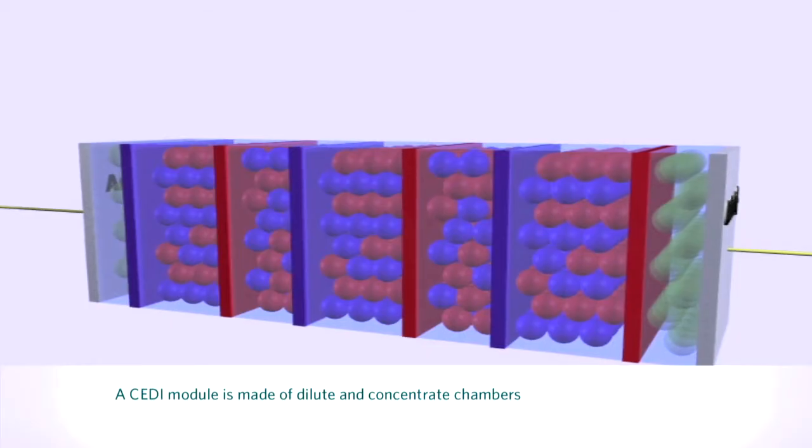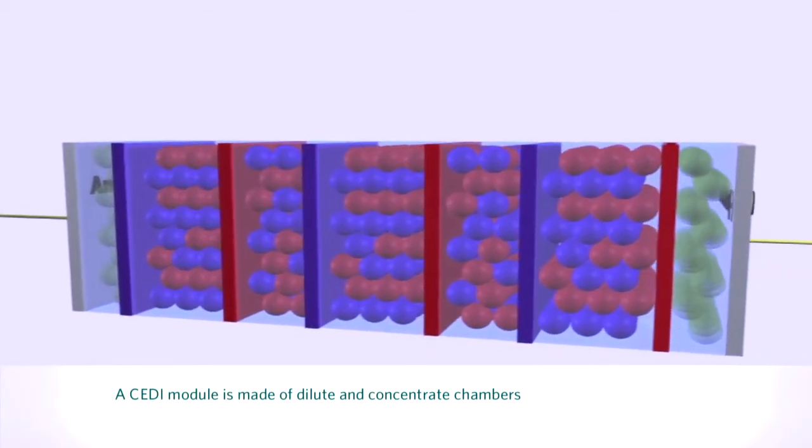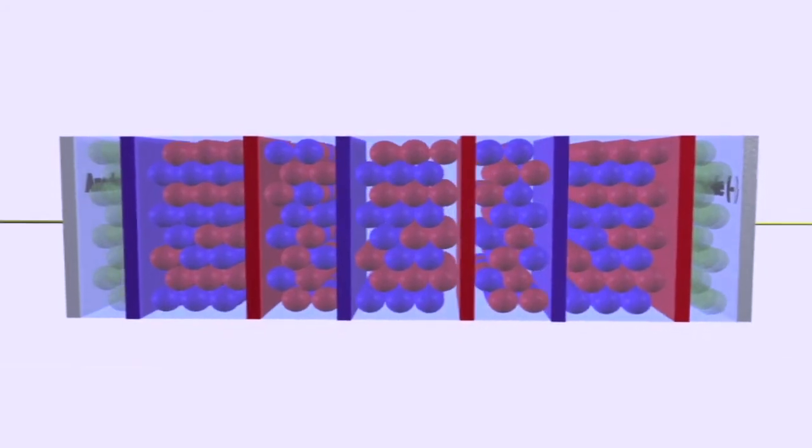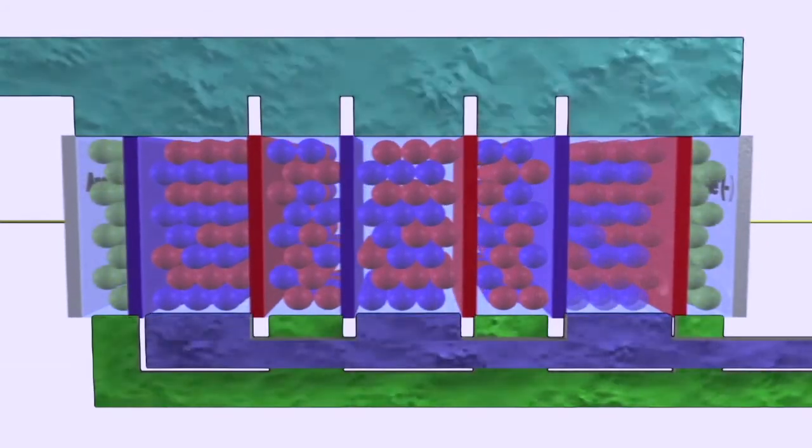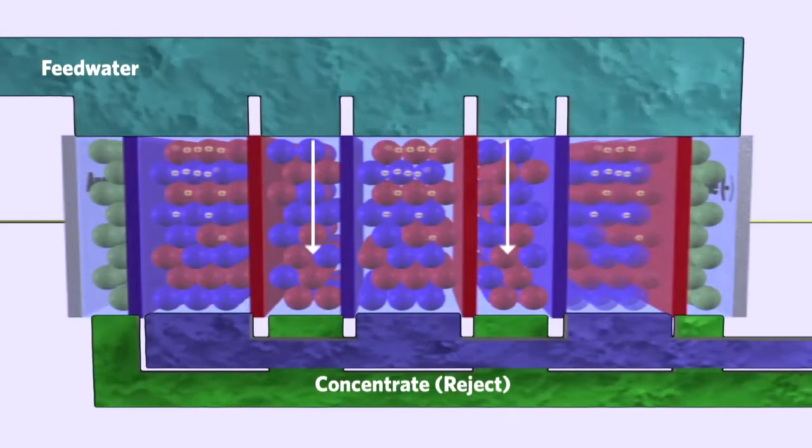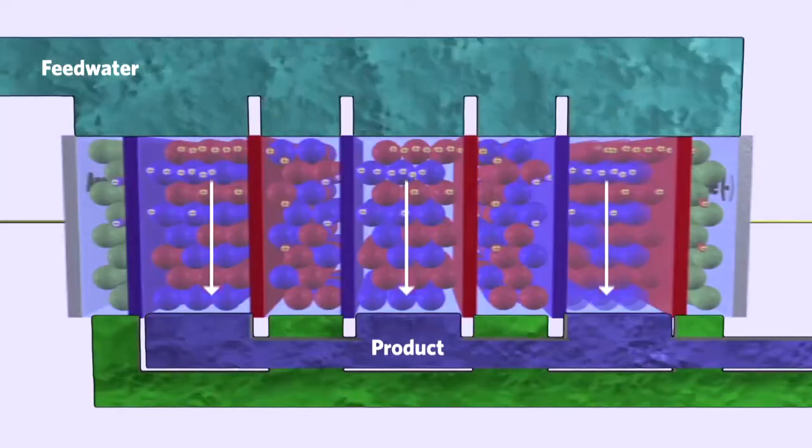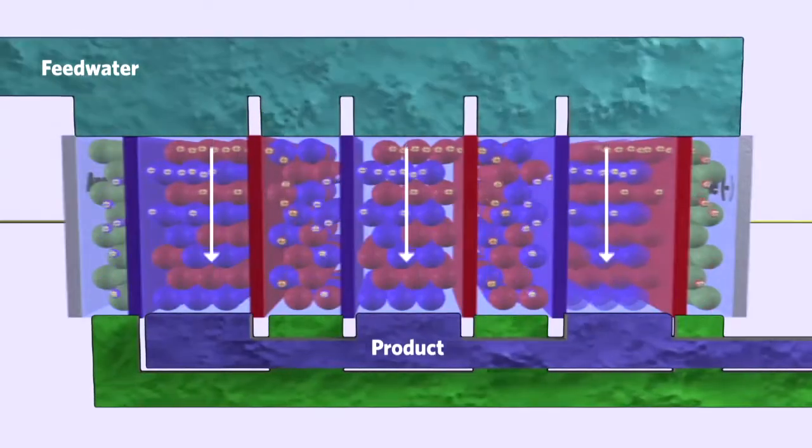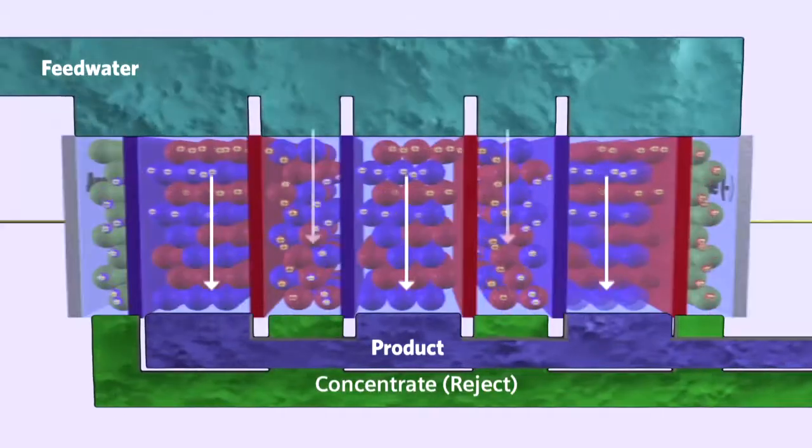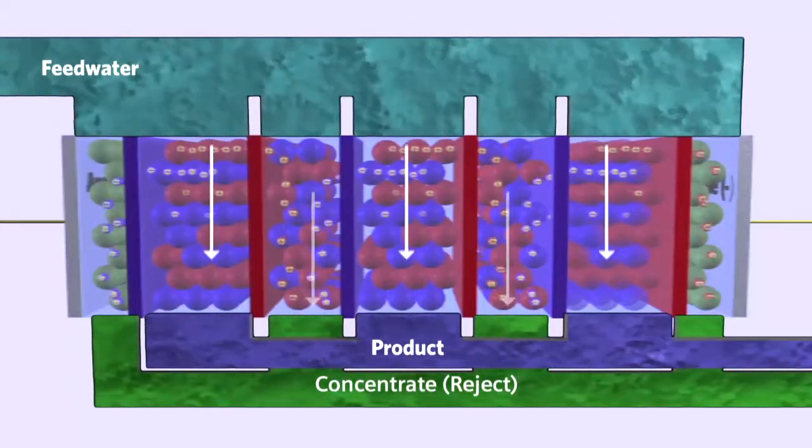we create a series of water purification compartments, alternating with compartments where the ions are concentrated. As feed water is pumped into the system, it is diverted into separate compartments, mainly the concentrating compartment and the purification or dilute compartment. These water streams remain separated throughout the process, because only ions can pass through the membranes.